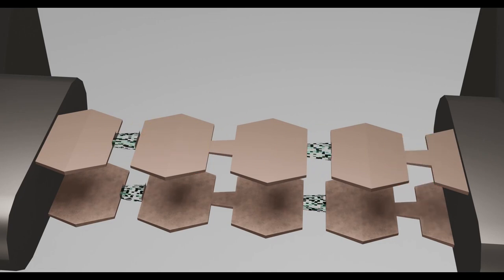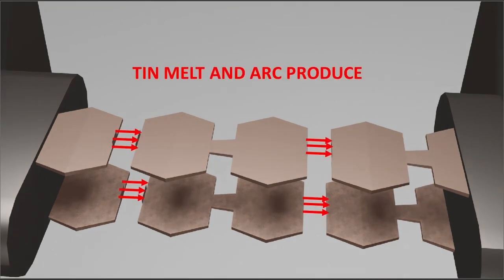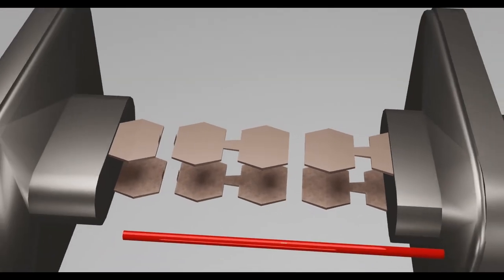material. As the tin melts, it opens the circuit, but due to the very high amount of current passing through the element, it produces an arc. Hence, we need to stop the arc to stop the flow of current.